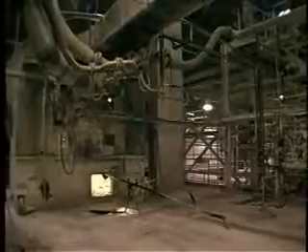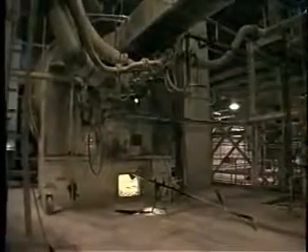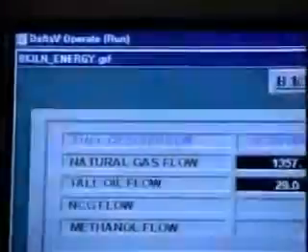In the temperatures, there were excursions on both the feed end and hot end controls. With the multiple fuels that we burn, alone or with one another, the rates would start to chase themselves. It would just go out of control. It was always back into the manual mode.